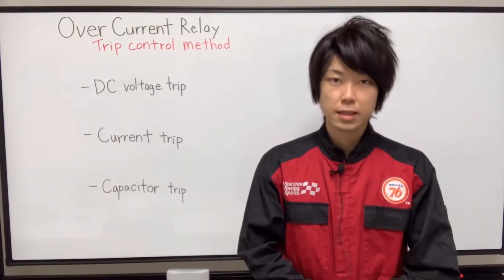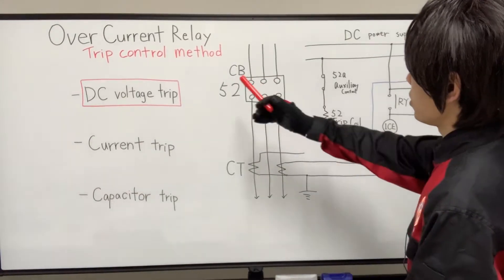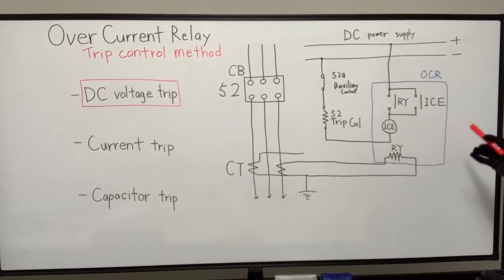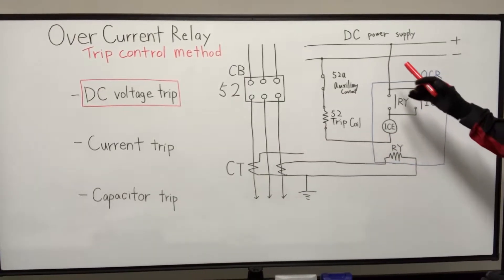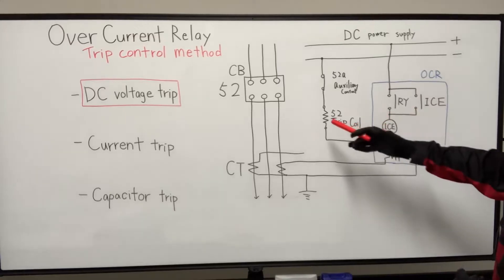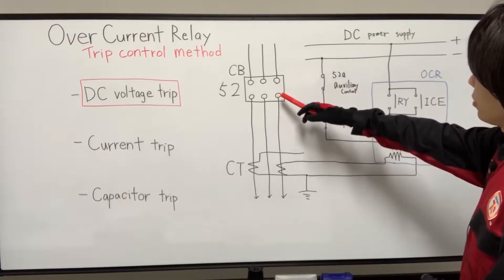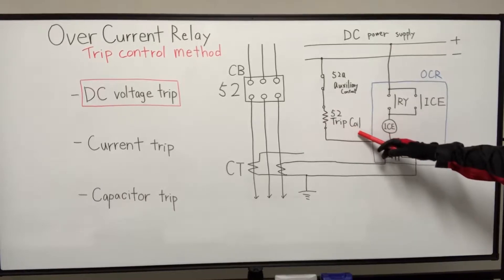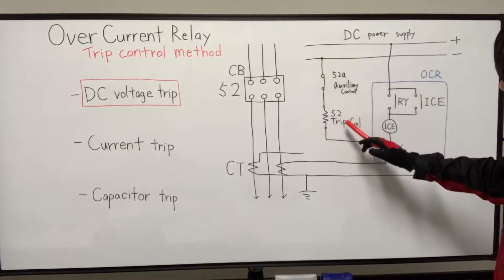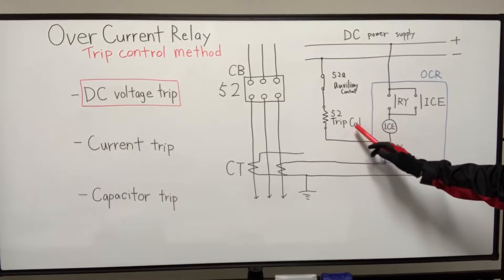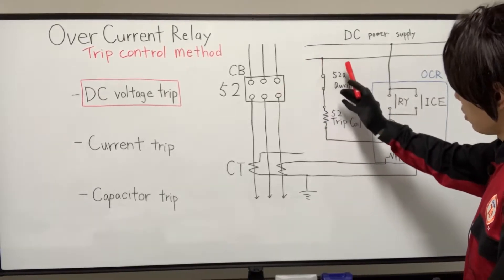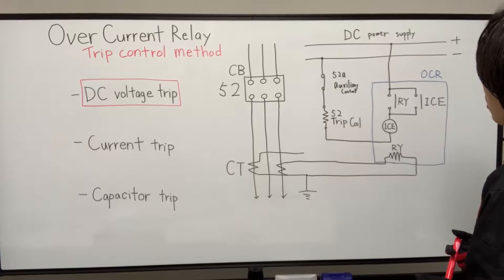So let's get started. Let's start with DC voltage trip. In this method, control circuit is external DC power supply. And as shown in this diagram, the circuit breaker 52 contains the trip coil which led to 52 trip by being energized himself. I mean, if trip coil is energized, 52 will trip.